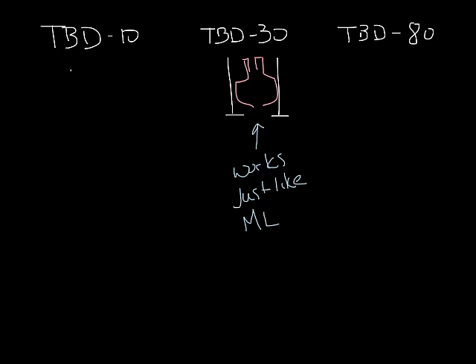The TBD10 pattern controller looks something like this. So in this case you can take the pattern controller and move it from the right side or to the left side so that you can make it blow in either direction. But when it's set on the right side like this you get the low pressure zone here and the air holds to the ceiling and moves to the right.